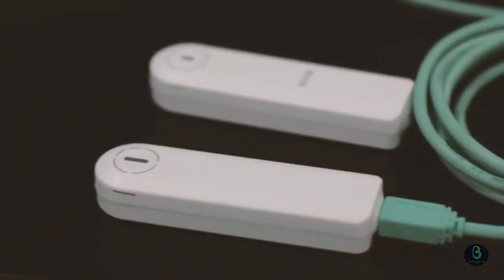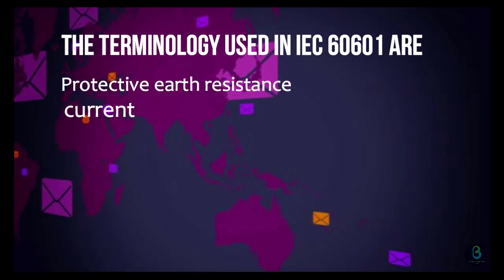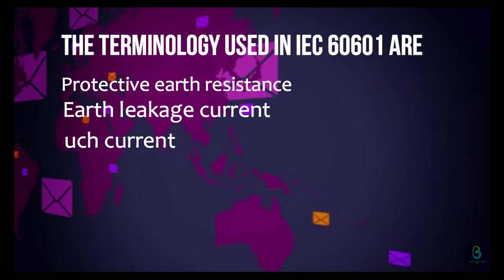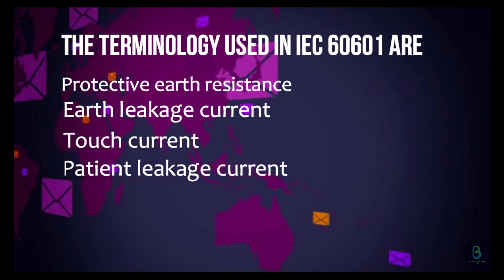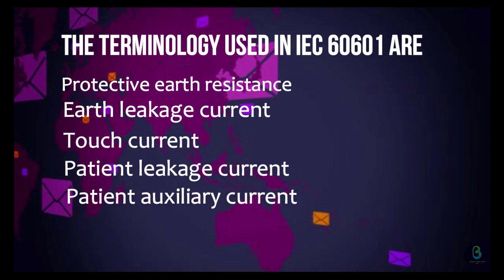The terminology used in IEC 60601 are Protective Earth Resistance, Earth Leakage Current, Touch Current (Formerly Enclosure Leakage Current), Patient Leakage Current, Patient Auxiliary Current, and Mains on Applied Part.